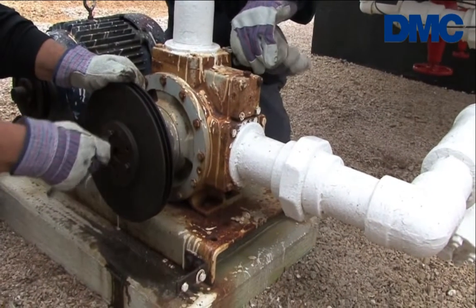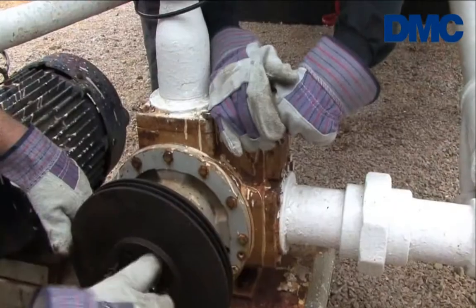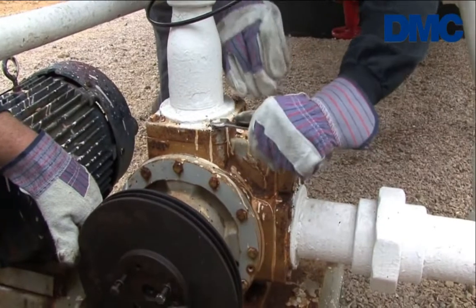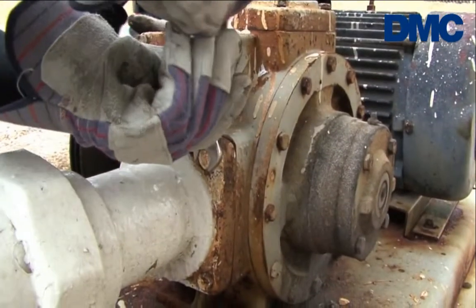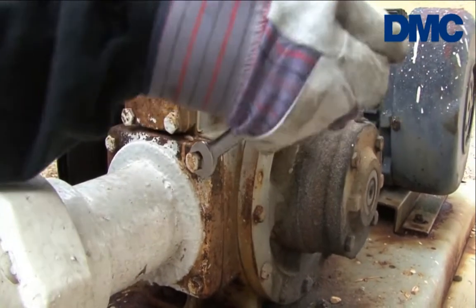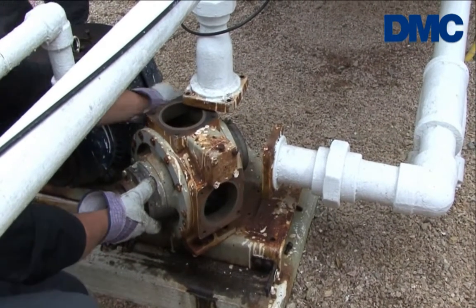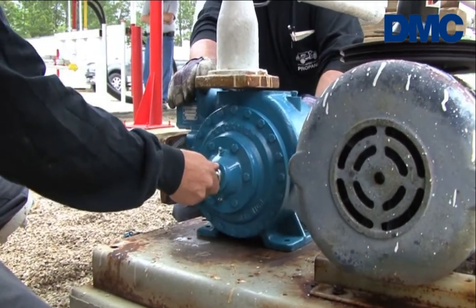The most impressive part of the pump is the ease of installation. There's no re-piping required because of the way the casing of the new Blackmer 3021 series was designed. No pipe wrenches are required — just regular wrenches and maybe a gear puller to pull the sheave off, which is something all propane guys have. The motor doesn't come off, no electrical work. Basically, you've eliminated any subcontractor from the process. The same horsepower motor that was pulling the competitive model will pull the Blackmer pump.